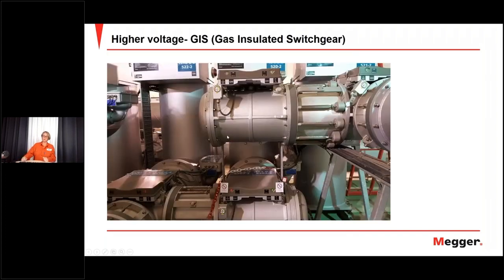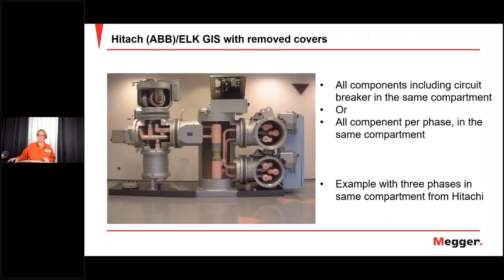And we also on high voltage have GIS, gas insulated switchgears. And here you have an example of that. As you can see, you have a metal cover over the whole switchgear, and it's even hard to realize where the actual breaker is situated. But we get some help here, so we have opened up the covers so you can see the circuit breaker in the middle. And you can also see here that it's three phases in the same compartment, but it can also be separate compartments, certainly for higher voltages.